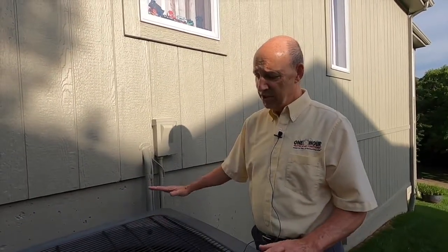What we want to do is size that air conditioner based on your home, based on the exposures that you have, based on the temperatures that you want to maintain. We want a properly sized air conditioner to maintain that kind of temperature. We want a certain amount of runtime out of this air conditioner. Not only does this air conditioner cool the air, but this is also what's dehumidifying the air in the summertime. A properly sized air conditioner is going to have the proper runtime so we can actually be dehumidifying the air inside. If it were, gee, let's just get a bigger one, well, now we've got an air conditioner that doesn't physically run the same amount of time as a properly sized air conditioner, and so it's going to dehumidify less than the smaller air conditioner.